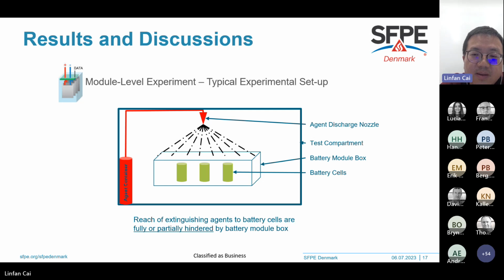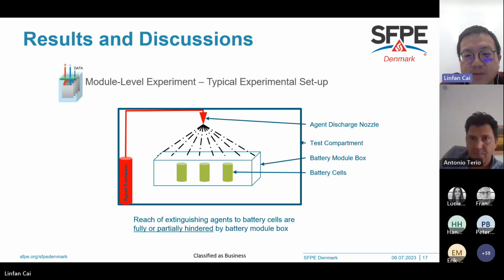The cooling effect mentioned earlier for the cell level experiment may or may not apply to the module level experiment. One additional point is that the material of the module box also plays a part. For instance, if the module box is combustible, and the fire is able to melt it, that creates space for the extinguishing agent to seep through and reach the battery cells, which may help with cooling and internal fire extinguishing at the module level.